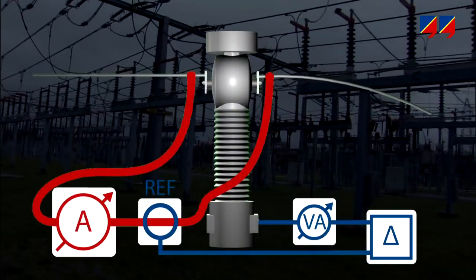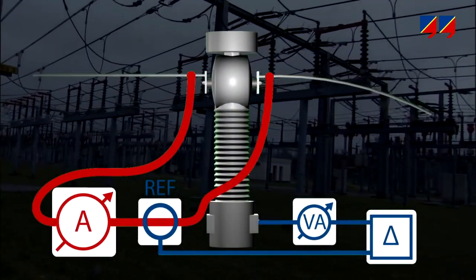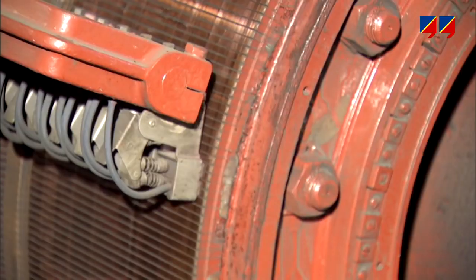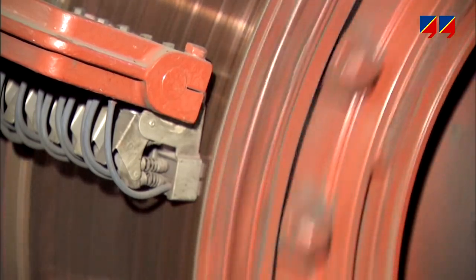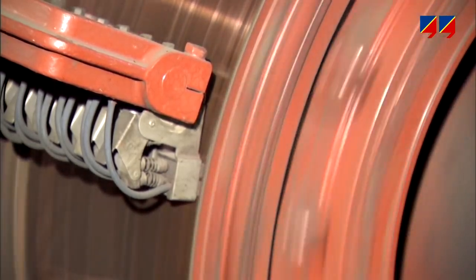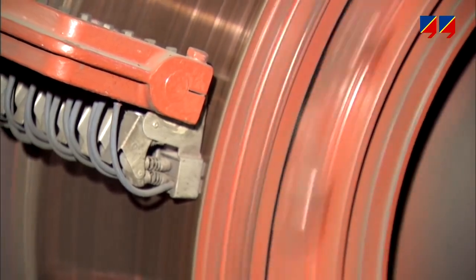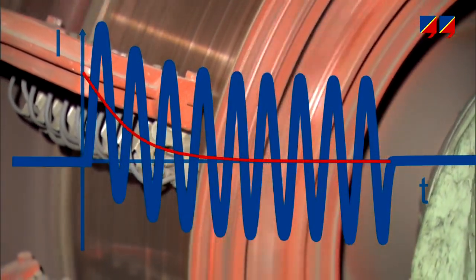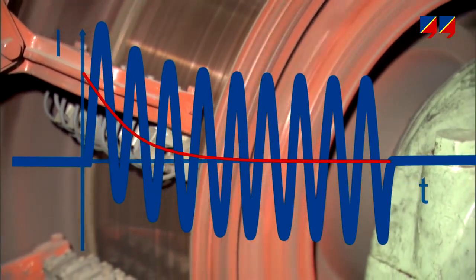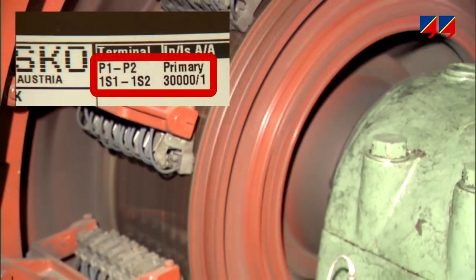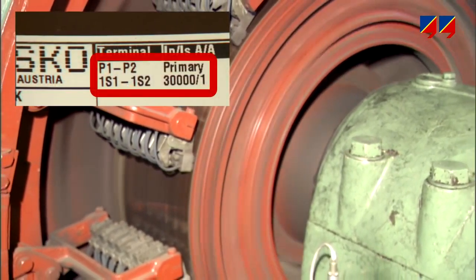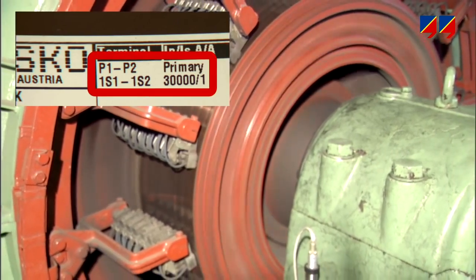This method is costly and laborious, particularly on-site, as heavy components need to be shipped and unwieldy cables are required for the current injection. Even this method reaches its limits where protection CTs designed for high short-circuit currents, high DC components in the fault current, or high primary time constants are involved. Such CTs require thousands of amps for testing, exceeding the largest current source's maximum output current.